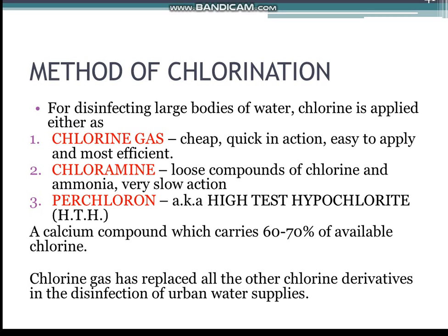Perchloron or high-test hypochlorite, HTH, is a calcium compound which carries 60 to 70% of available chlorine. Solutions prepared from HTH are also used for water disinfection. Chlorine gas has replaced all the other chlorine derivatives in the disinfection of urban water supplies.